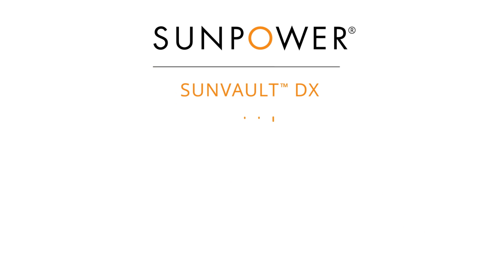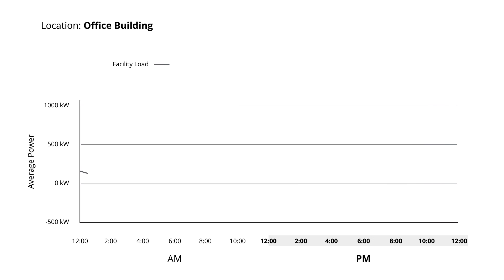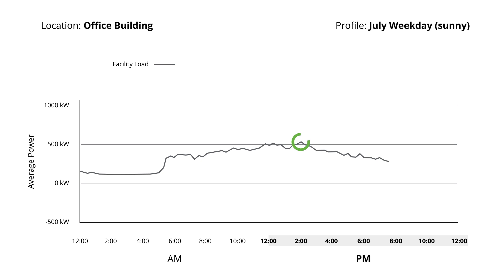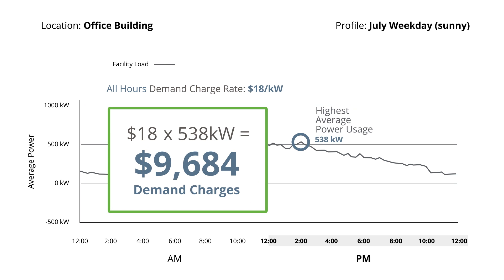Let's see how Sunvault DX storage intelligently analyzes facility load, solar production, TOUs, and utility rate structures, including demand charges, to save money. This graph illustrates an example energy load profile for an office building, showing the amount of power used from the utility grid over the course of a typical sunny workday in July. It ramps up as workers start coming in, continues to climb into the afternoon — the hottest time of the day when the AC system is hard at work — and then slowly declines until late in the evening. The facility's highest average power usage for the month occurs right around 2 p.m. and is 538 kilowatts. With an all-hours demand charge rate of $18 per kilowatt, that calculates to $9,684 per billing period.